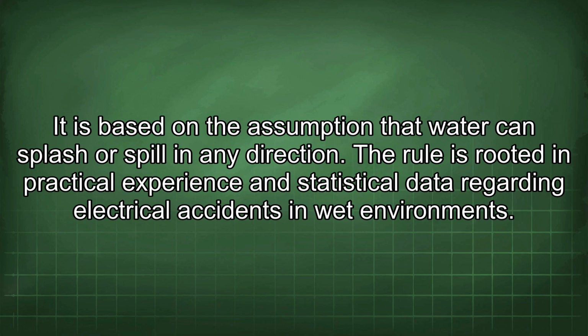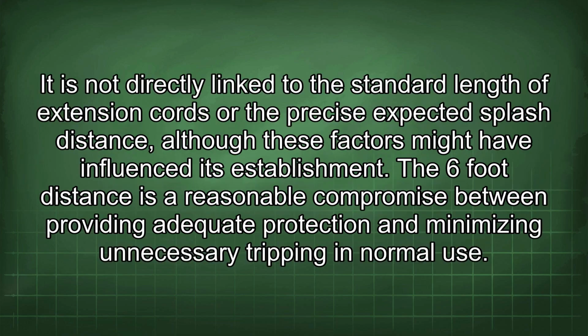The rule is rooted in practical experience and statistical data regarding electrical accidents in wet environments. It is not directly linked to the standard length of extension cords or the precise expected splash distance, although these factors might have influenced its establishment. The 6-foot distance is a reasonable compromise between providing adequate protection and minimizing unnecessary tripping in normal use.